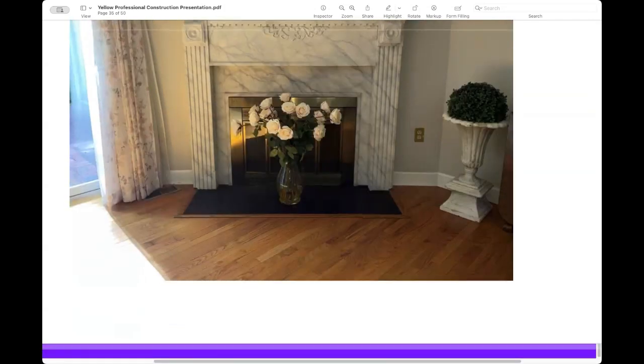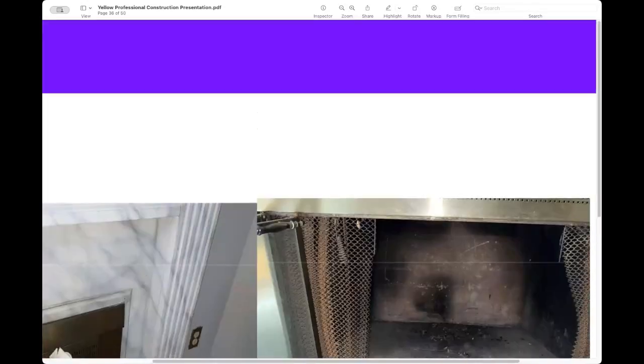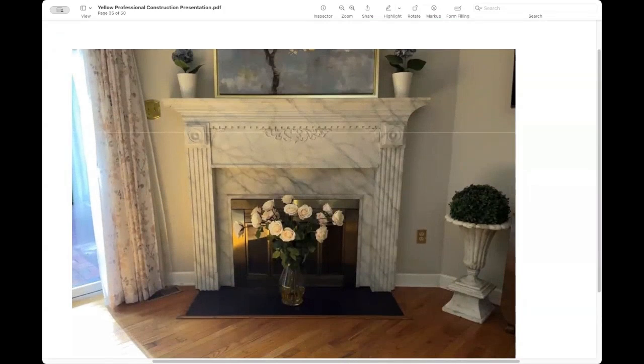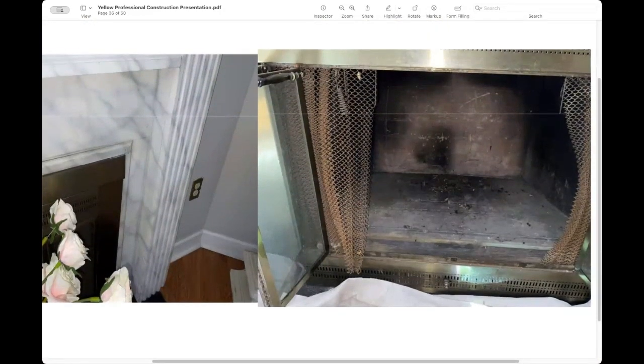Every single piece that looks like marble is plywood or trim board. Wow, so someone actually just spent a lot of time on YouTube and made a gorgeous decorative piece that could start a fire. That painting is wonderful. That faux marble is some of the best painting I've seen, but none of that is non-combustible.